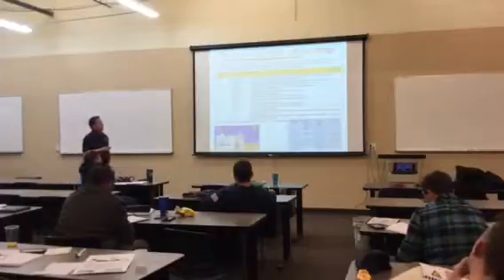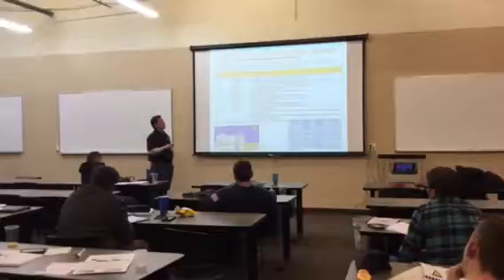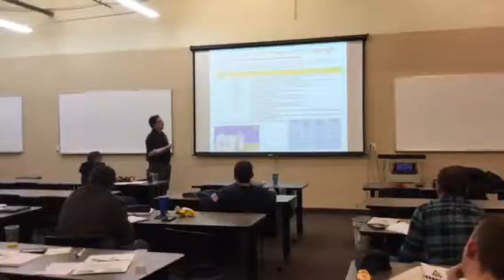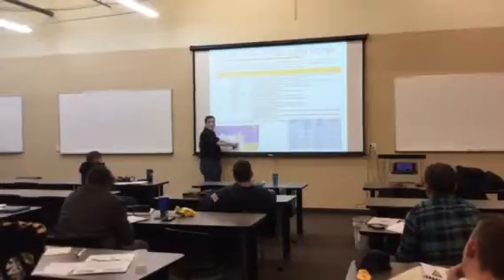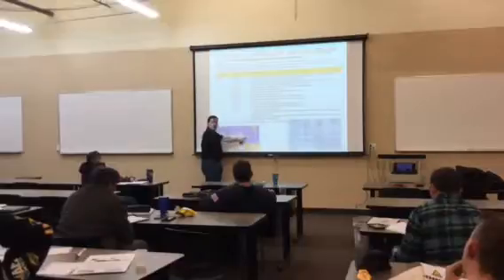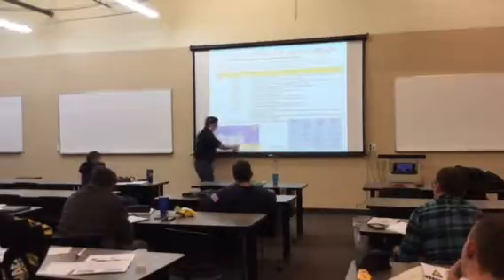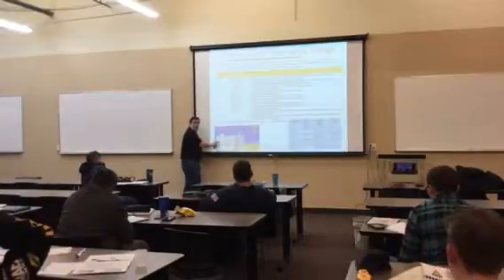This includes equipment and fixed installations such as switchgear and polyphase motors. Polyphase would be 3-phase. Bus and feeder in industrial plants. Feeders and short branch circuits. Appliance outlets with short connections to the service entrance. This is where we're concerned right here. If we're in a mechanical room, either in a home or a building, and it's in this room right here, which is not uncommon, we are very close to the service entrance, and this is a higher risk category than if we were working on the exact same type of appliance on the other end of the building. You've got to pay attention to where you are proximity-wise.